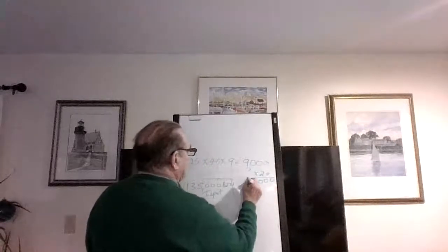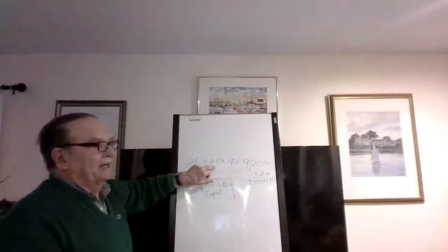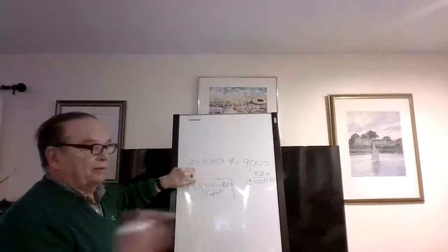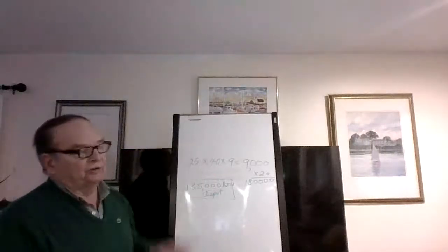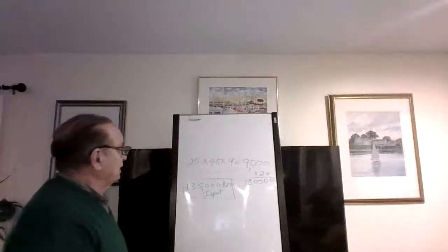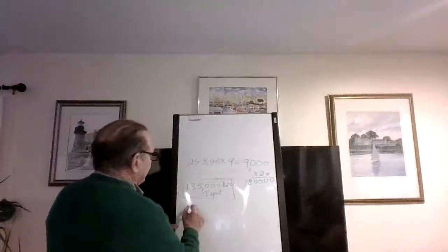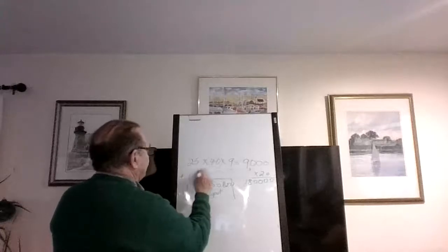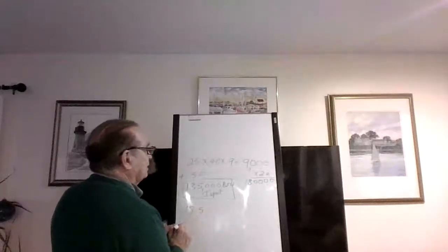Okay. This size basement, which is big, that 40 is big. That's getting up around ranch house size. 25 front to back, it's about right. 9-foot ceiling, I'm being a little generous. It's usually closer to 8. All right. But you throw in a water heater, a 60,000, you make it a 50. So you got 135 plus 50, right? Now what? 185,000, right?